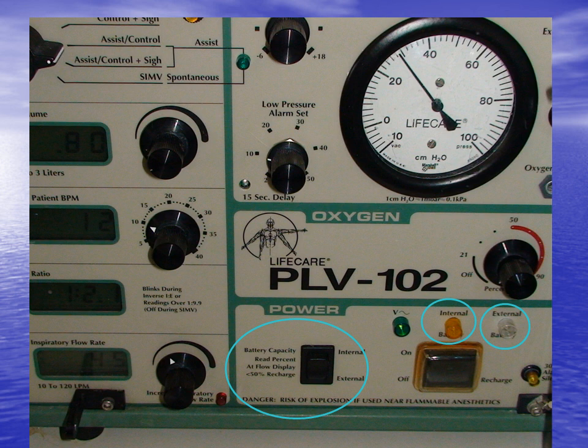This vent also has an internal battery that can operate the vent for approximately 1 hour. An amber LED is lit when the internal battery is being accessed. Both the internal battery and the external battery will automatically recharge when the unit is plugged into a wall outlet. The rocker switch will show the capacity left in these batteries, expressed as a percentage, but only if the vent is not plugged into an AC outlet and is therefore utilizing battery power.